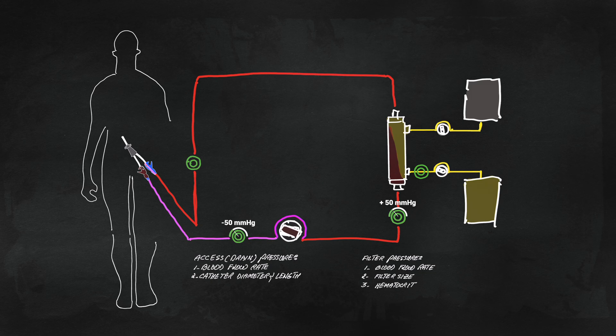Next is the filter pressure sensor between the blood pump and the filter. Its baseline pressure is dictated by the blood flow rate, the filter size, and blood viscosity, and if anything is obstructed downstream.